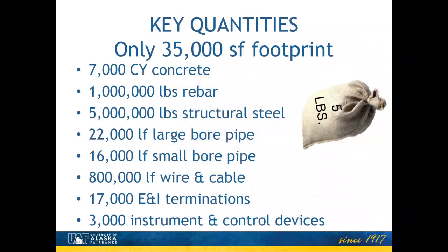So in that building, there's a lot of stuff. The footprint on the ground of it is only 35,000 square feet, but there's a whole lot of things in that 35,000 square feet. There's over 7,000 yards of concrete, about 1 million pounds of reinforcing steel, over 5 million pounds of structural steel, 22,000 feet of pipe greater than 2 inches, almost 16,000 feet of pipe less than 2 inch, and 800,000 feet of wire and cable. You look through the place, there's cable trays all over the place that are just packed with wire. There were over 17,000 electrical and instrumentation terminations in there, and there's over 3,000 instrument devices that provide information on the plant and provide control to it. So there's a whole lot of stuff packed in a really small box.